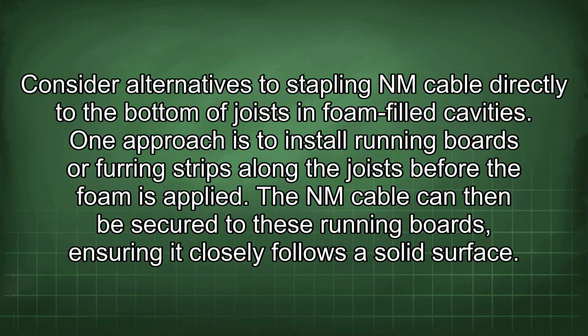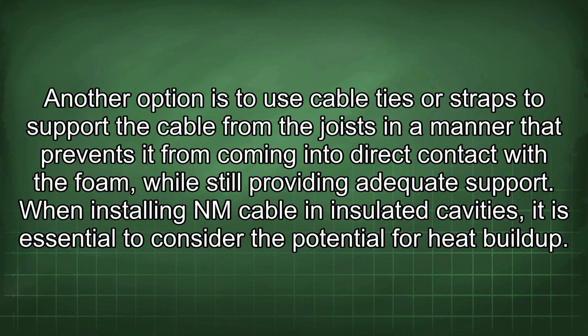Consider alternatives to stapling NM cable directly to the bottom of joists in foam-filled cavities. One approach is to install running boards or furring strips along the joists before the foam is applied. The NM cable can then be secured to these running boards, ensuring it closely follows a solid surface. Another option is to use cable ties or straps to support the cable from the joists in a manner that prevents it from coming into direct contact with the foam, while still providing adequate support.